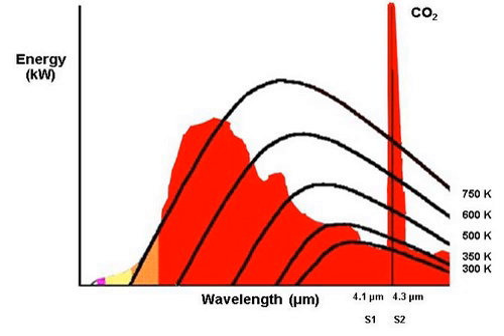Not all manufacturers of flame detectors use sharp filters for the 4.3 micrometers radiation and thus still pick up quite an amount of sunlight. These cheap flame detectors are hardly usable for outdoor applications. Between 0.7 micrometers and approximately 3 micrometers there is relatively large absorption of sunlight. Hence, this frequency range is used for flame detection by a few flame detector manufacturers in combination with other sensors like ultraviolet, visible light, or near-infrared.